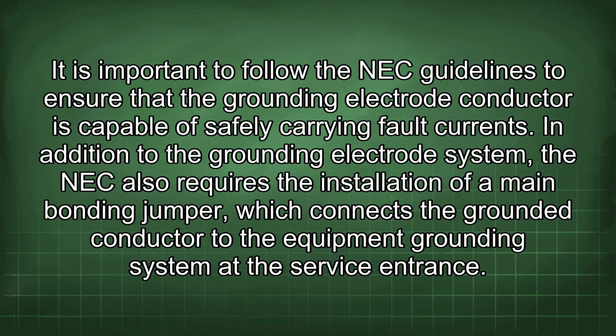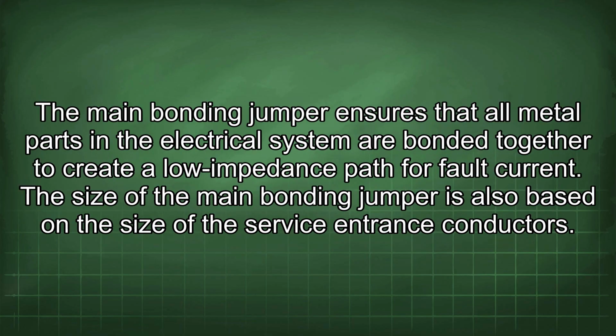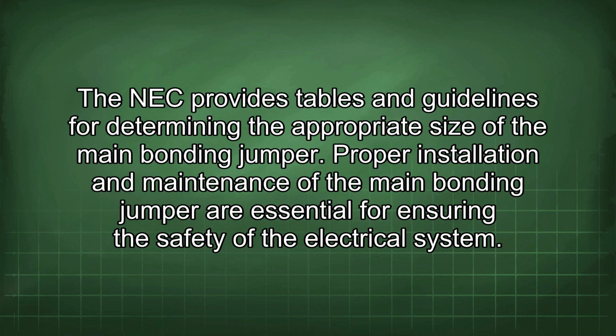which connects the grounded conductor to the equipment grounding system at the service entrance. The main bonding jumper ensures that all metal parts in the electrical system are bonded together to create a low impedance path for fault current. The size of the main bonding jumper is also based on the size of the service entrance conductors. The NEC provides tables and guidelines for determining the appropriate size of the main bonding jumper. Proper installation and maintenance of the main bonding jumper are essential for ensuring the safety of the electrical system.